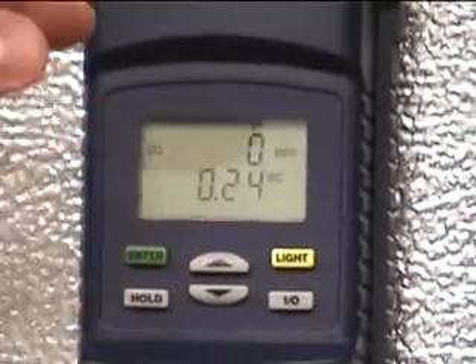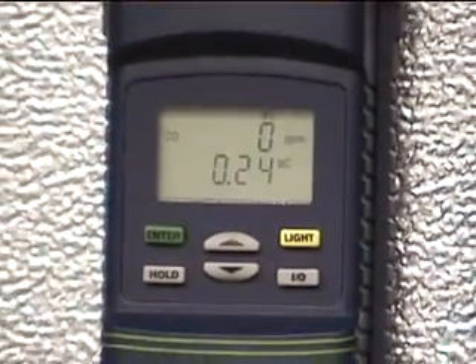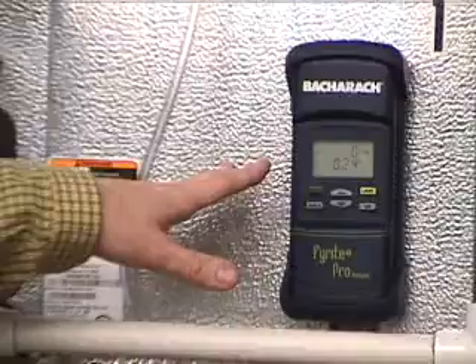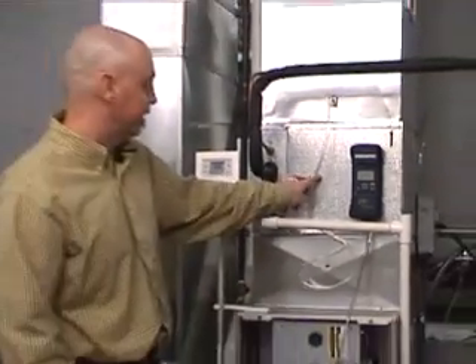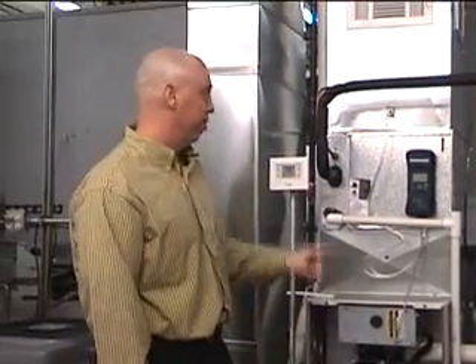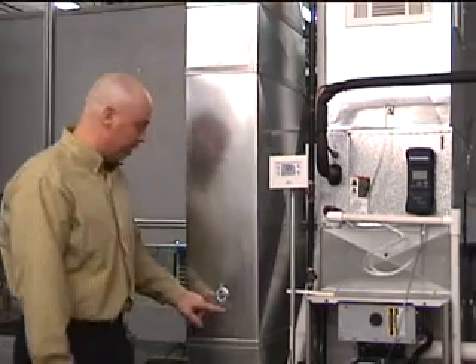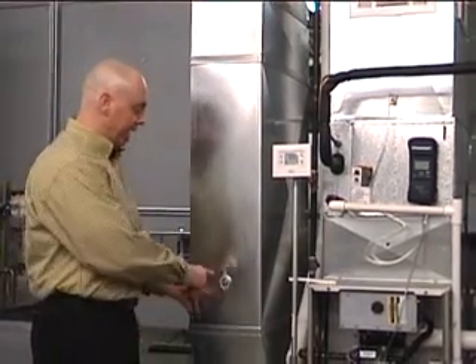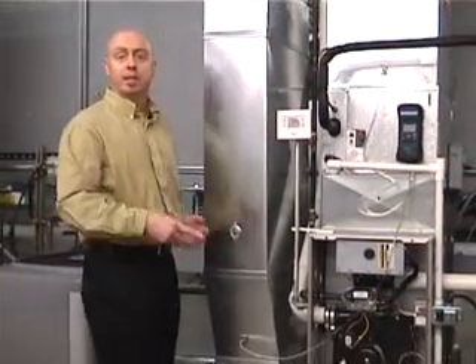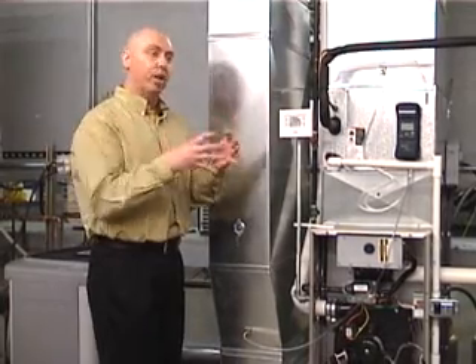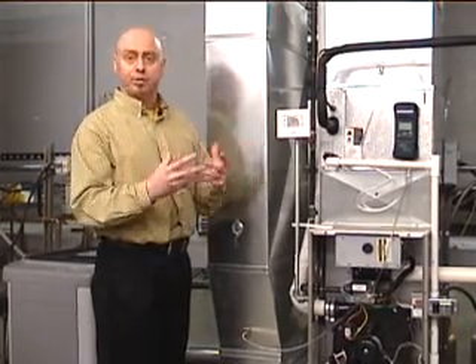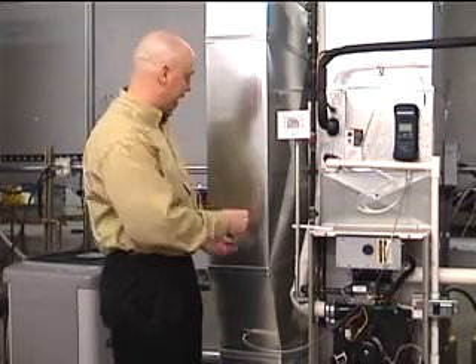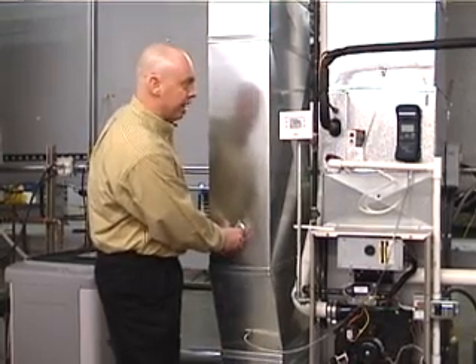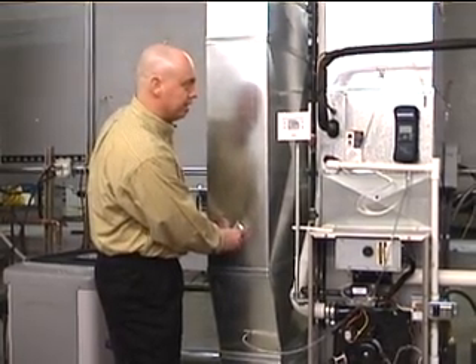So that's pretty low. That's a pretty good number for heating. It's really low, but it's a false positive reading because that's not accurate, because I am not taking into consideration this coil or the filter. Now, since this is a testing facility, I have put a damper in here. So what I'm going to do is simulate some shrunken return duct, high resistance in the return duct. So I wanted to show you what would happen if I turn this and I block some of the air off.